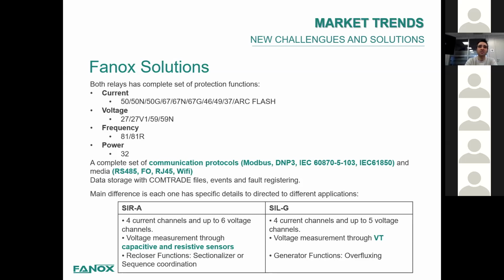As I said, this has overcurrent protection as well as voltage protections, and frequency, undercurrent, overcurrent, and rate of change of frequency, and power control. These relays come with a complete set of communication protocols: Modbus, 103, 61850, and also can be in different media: Wi-Fi, RS-485, fiber optics. Again, a complete storage through COMTRADE and events of all registering. And the main difference between these two relays is that the SIR-A has 4 current channels and up to 6 voltage channels, but it works with sensors, both capacitive and resistive. It also has recloser functions, sectionalizer or sequence coordination.